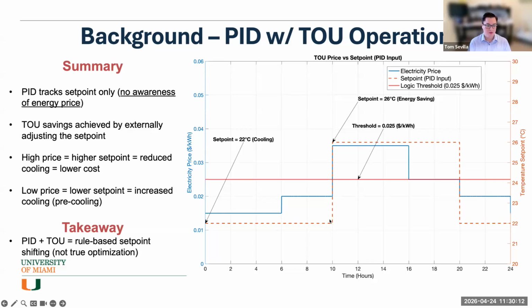One takeaway here is that it's rule-based set point shifting, so we're not truly optimizing anything. You can get as complex as you want with the logic, but that takes away from the simplicity of setting up PID for an HVAC system. Also, what happens in areas where there isn't a clear distinction between the logic threshold and what counts as high or low pricing? We're not taking advantage of those changes or handling them in any way.